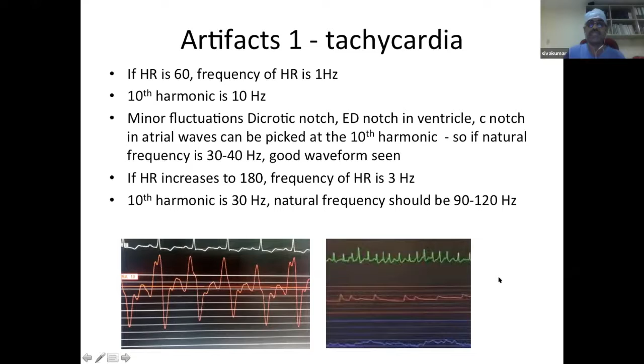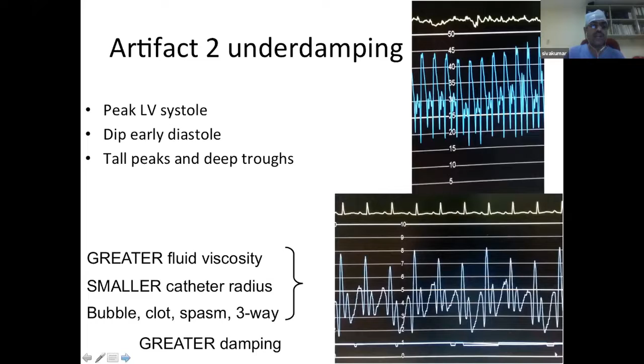Second is underdamping. Underdamping means too many overshoots: the peak of LV systole, whatever the peaks and troughs, they are overshot. Now, how to avoid overdamping? Greater fluid viscosity: if there is a small amount of contrast or blood, it will lead to overdamping. Small catheter radius will lead to overdamping. A bubble, clot, spasm, using multiple 3-ways. These are all causes of overdamping. So we should try to avoid over and underdamping.